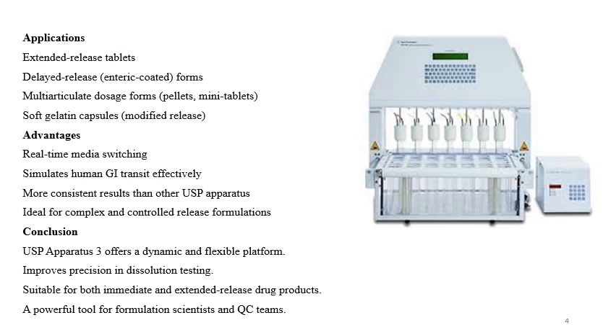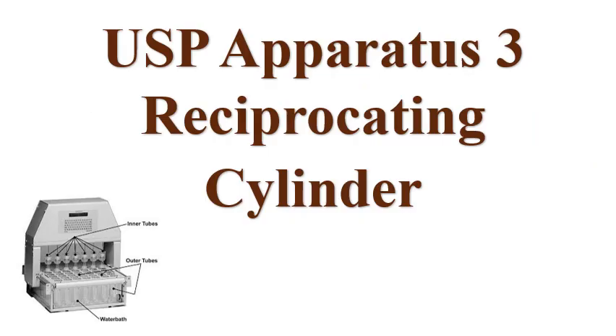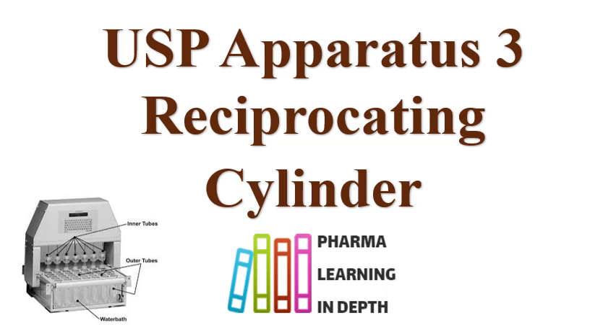Advantages of this apparatus include real-time media switching, effective simulation of human GI transit, and more consistent results compared to other USP apparatus. It is ideal for complex and controlled release formulations. In a single run, you can study the effect of pH on the same formulation. USP apparatus 3 offers a dynamic and flexible platform for dissolution studies under various pH conditions, suitable for both immediate and extended release drug products. Formulations made with hot melt extrusion containing higher amounts of polymer can also be tested using this apparatus.